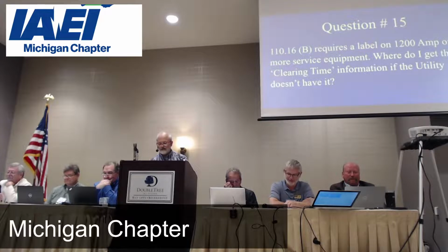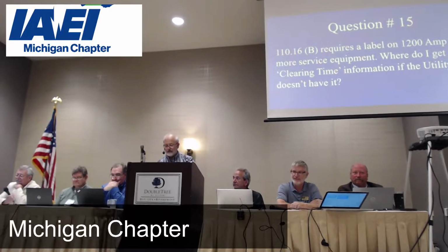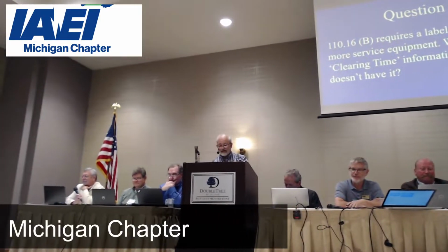110.16(B) requires a label on 1200 amp or more service equipment. Where do I get the clearing time information if the utility doesn't have it? Okay, well, generally the utility isn't going to have it. It's not a utility function.